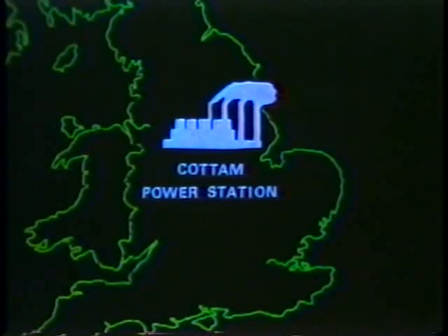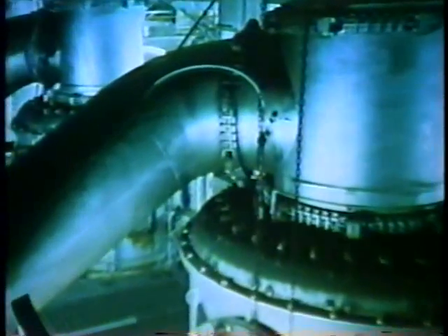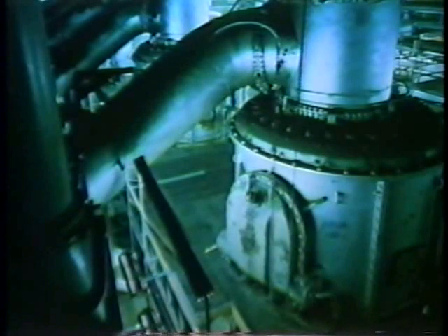KVB was alerted to this research in 1973 as it supported their own views and investigations of early warning systems. In 1974, collaboration with the British on a system design began. Successful testing of a prototype system in 1975 confirmed the British findings. The first operational system was installed at Cayuga in 1978 for Public Service Indiana. Two years of operating experience at PSI found that rising carbon monoxide without corrective action invariably resulted in a fire condition. Conversely, instances of rising carbon monoxide that were responded to promptly resulted in a resumption of normal operation. In all cases, a minimum of 1 hour warning time resulted.